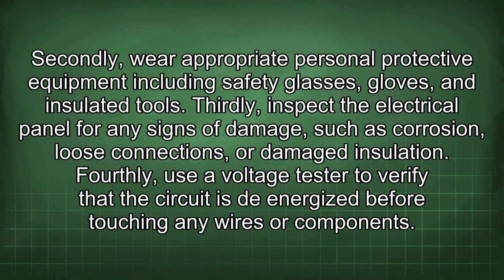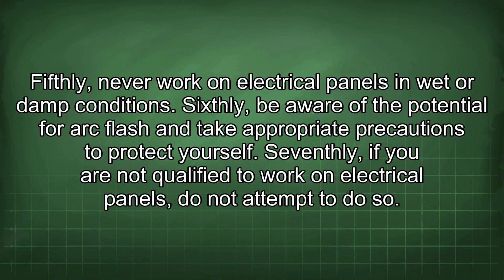Thirdly, inspect the electrical panel for any signs of damage such as corrosion, loose connections, or damaged insulation. Fourthly, use a voltage tester to verify that the circuit is de-energized before touching any wires or components. Fifthly, never work on electrical panels in wet or damp conditions. Sixthly, be aware of the potential for arc flash and take appropriate precautions to protect yourself. Seventhly, if you are not qualified to work on electrical panels, do not attempt to do so.